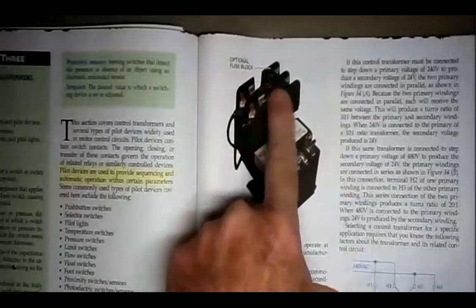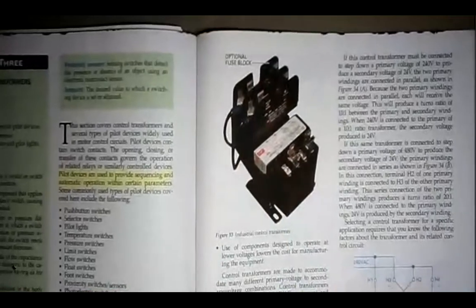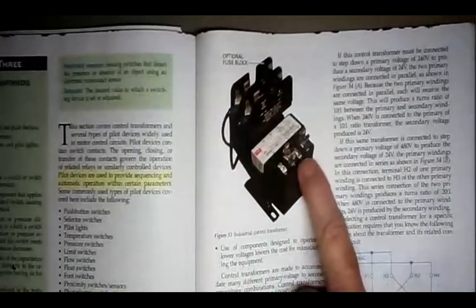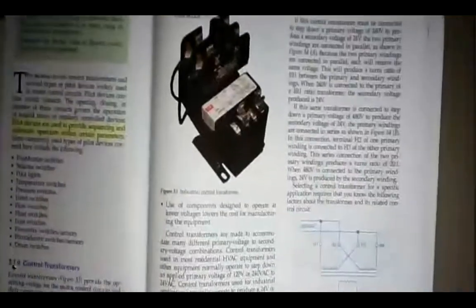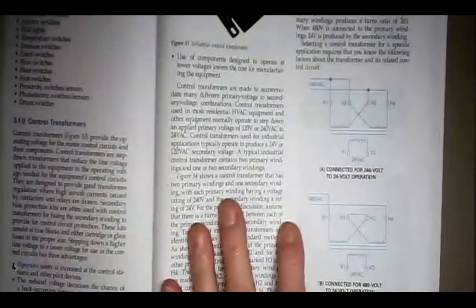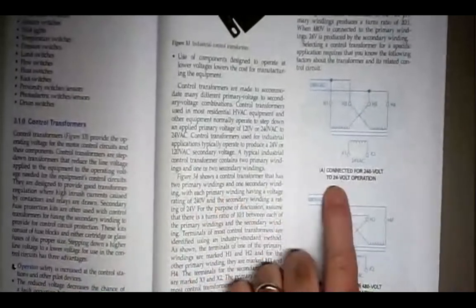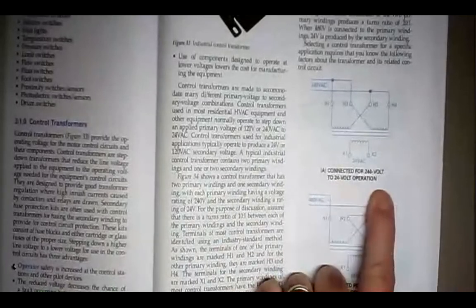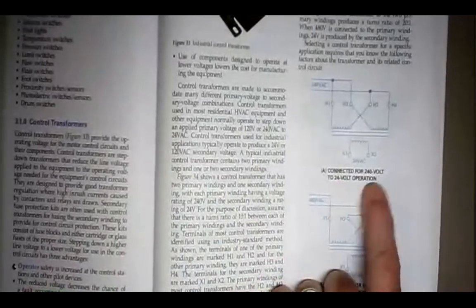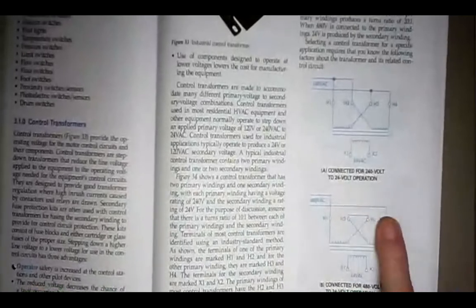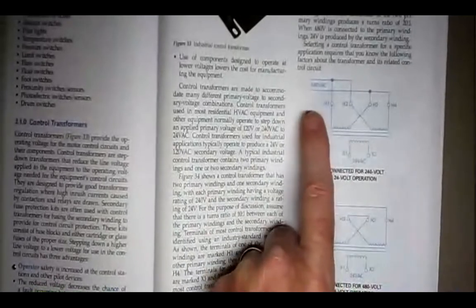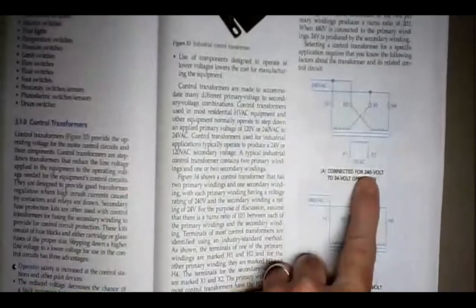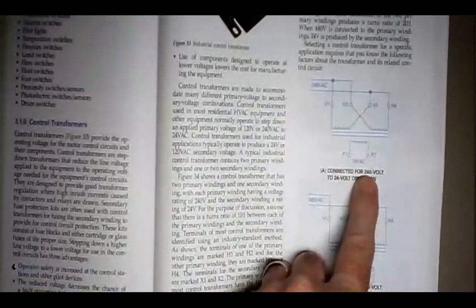Okay, so here's a transformer with a fuse holder. That's for primary protection, and they can even have a fuse here for secondary protection. These are called control transformers. Control transformers usually try to have an output of 120 volts, but here it's saying that they've got this connected for 240 volt to 24 volt operation. They're actually using this to step the voltage down to 24 volts on the secondary.